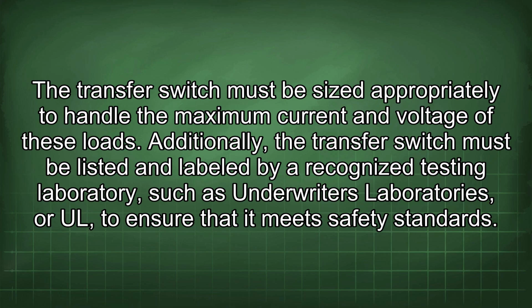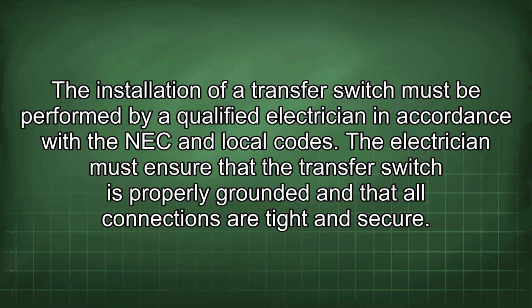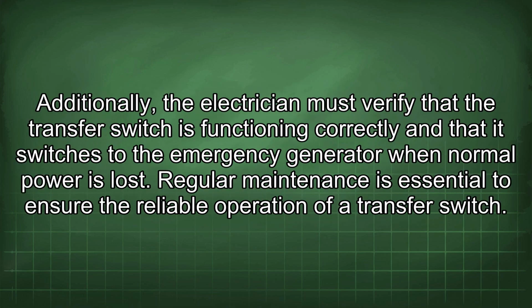Additionally, the transfer switch must be listed and labeled by a recognized testing laboratory, such as Underwriters Laboratories, or UL, to ensure that it meets safety standards. The installation of a transfer switch must be performed by a qualified electrician in accordance with the NEC and local codes. The electrician must ensure that the transfer switch is properly grounded and that all connections are tight and secure. Additionally, the electrician must verify that the transfer switch is functioning correctly and that it switches to the emergency generator when normal power is lost.